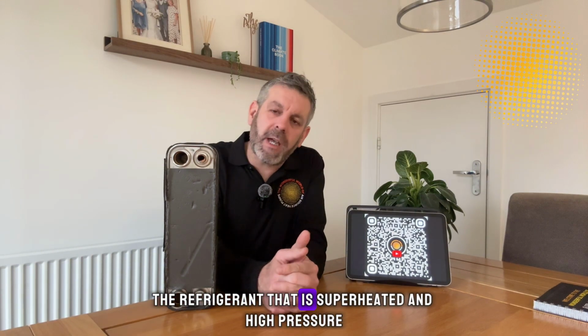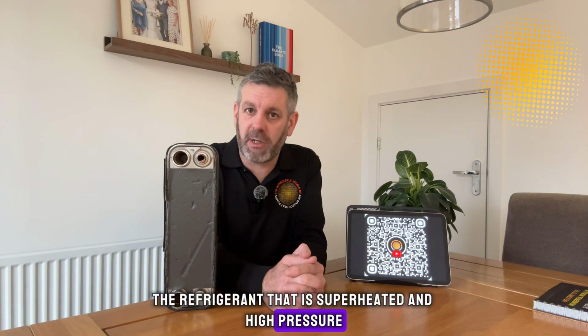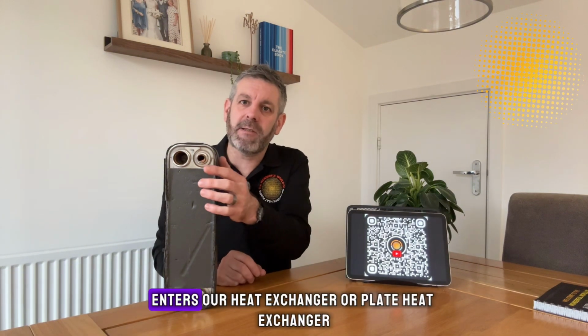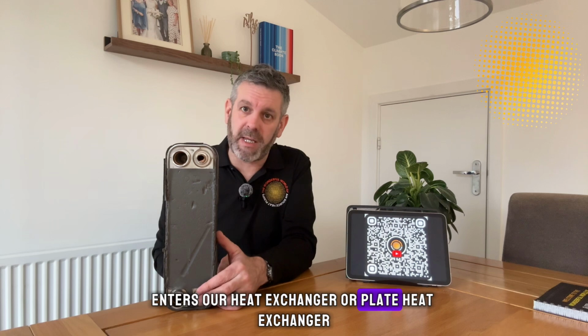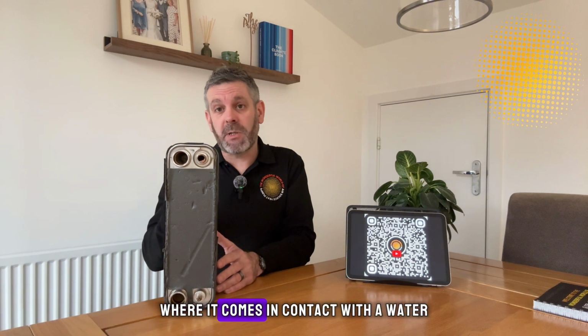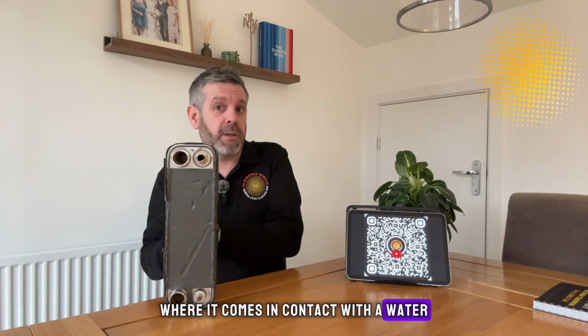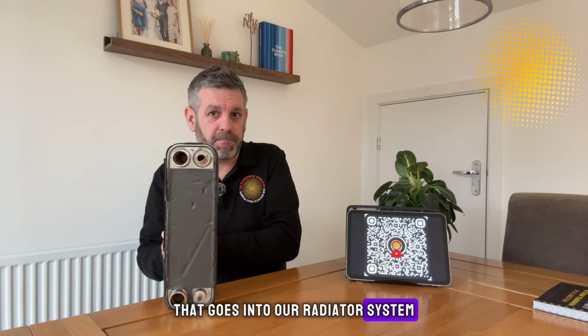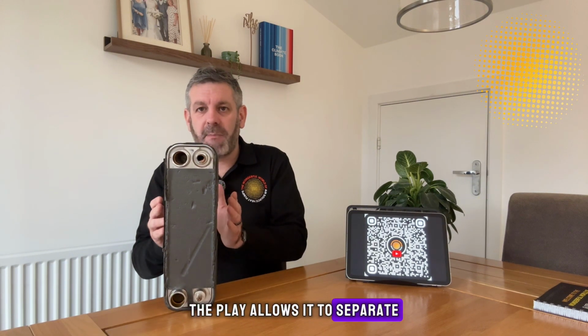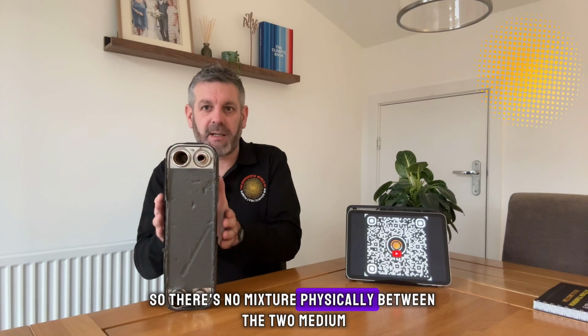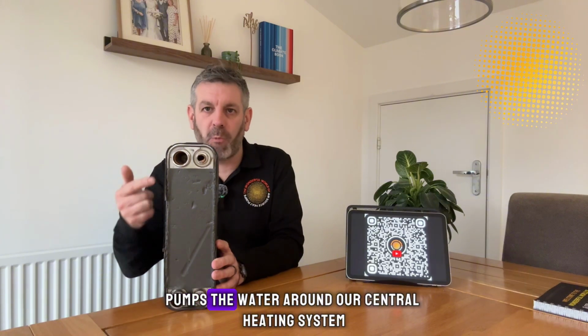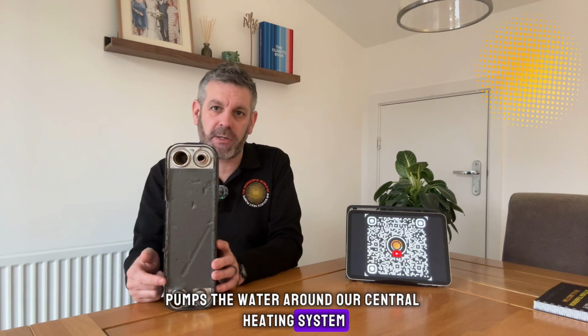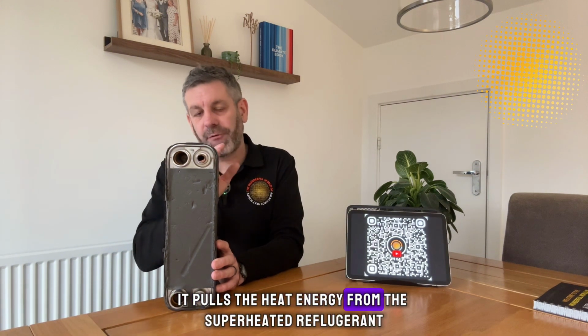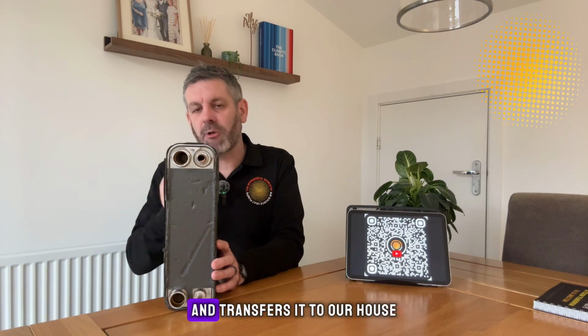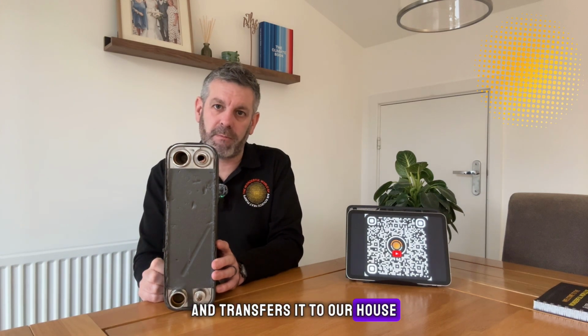The refrigerant that is superheated and high pressure that leaves our compressor enters our plate heat exchanger, where it comes in contact with our water that goes into our radiator system. The plate keeps them separate, so there's no physical mixture between the two mediums. As our central heating pump pumps the water around our central heating system, it pulls the heat energy from the superheated refrigerant and transfers it to our house.